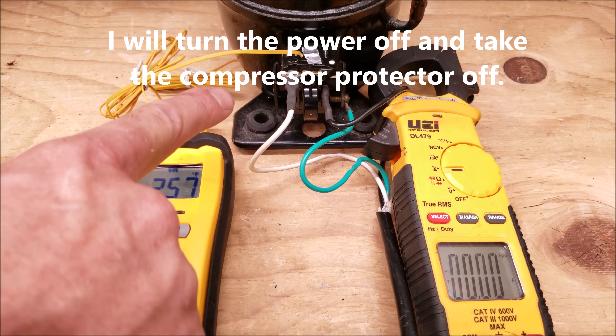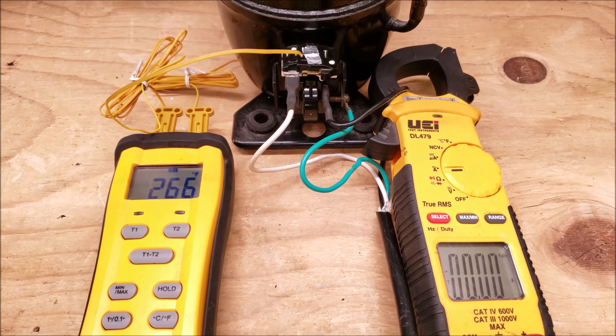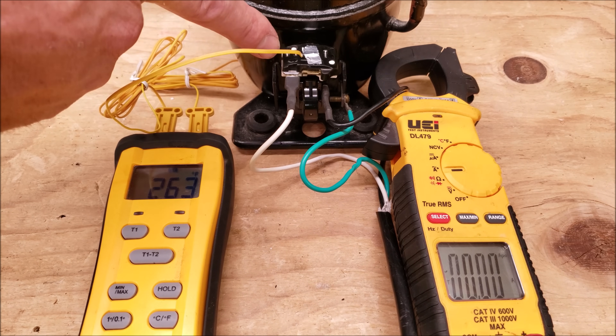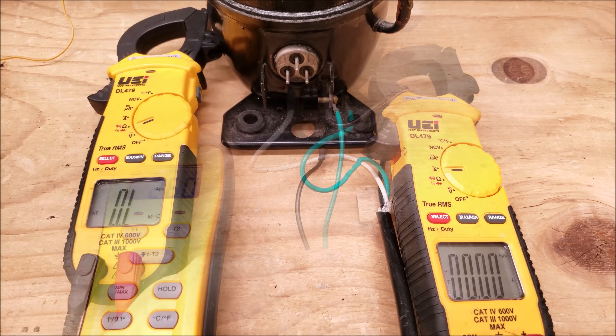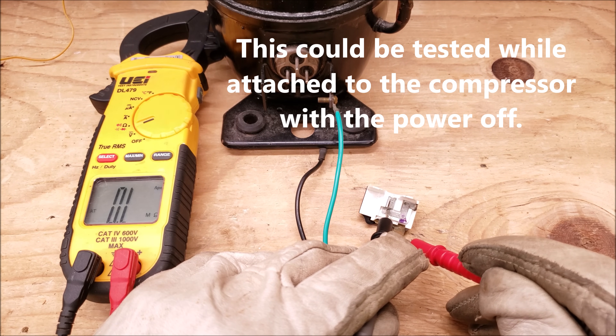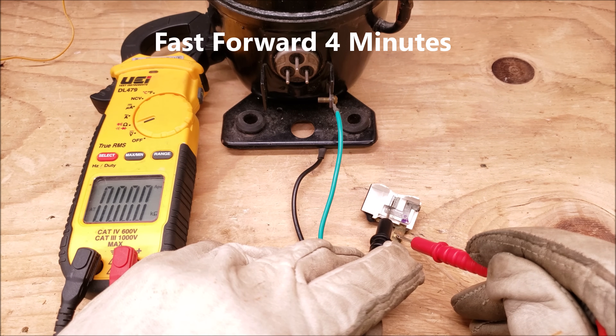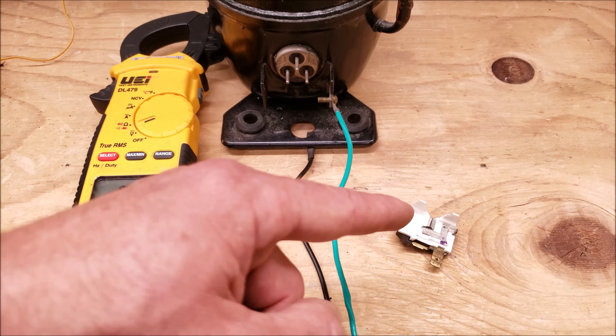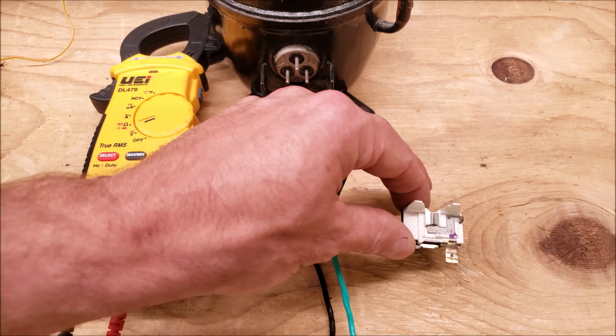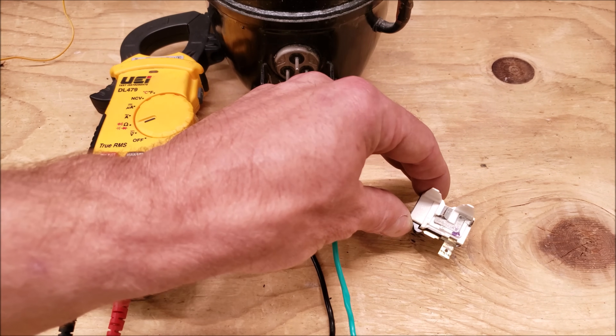I'm going to take this component off carefully because you can see how hot it is, and I'm going to read the resistance value across the two terminals — you can see that's going to read OL right now. This is very hot and we do read OL. So now it's open. If the compressor protector reads OL when it's cool, then that means it is bad and you would need another one, as this will stop that compressor from actually starting up.